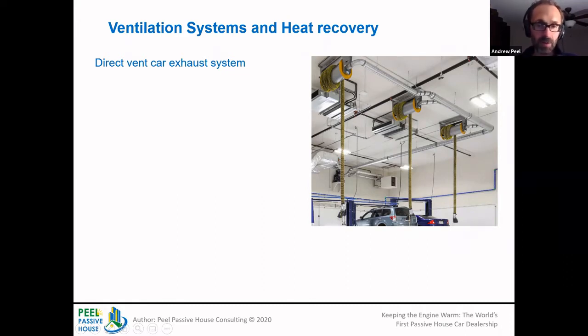The repair shop manager was not happy because he said that's going to disrupt service. It's one thing to clip onto the exhaust. They have a fairly easy method of doing that, but they didn't want to faff around with connecting a tube to the front. We thought we could avoid heating the makeup air by injecting it directly into the engine, but that wasn't going to go. And unfortunately, there's a high CFM rate per bay. We've got 6 bays, 400 CFM per service bay. So if all 6 bays are going at once, that's 2,400 CFM for a 16,000 square foot building. Compared to the background rate, that's a lot.